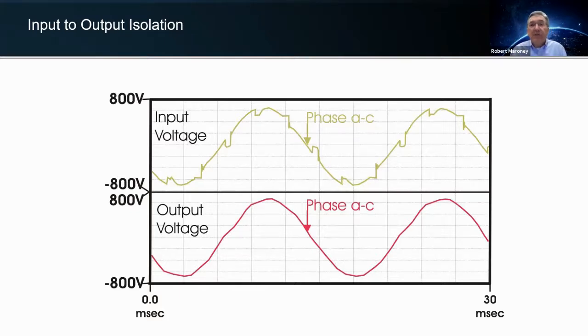Half a hertz off of 50 hertz, and that is adjustable, how sensitive your voltage and frequency are. We can adjust that tolerance from 1 to 15%, actually 20% low. We can go as low as 50% with support from the flywheel before we disconnect as well. But this gives you an idea of how we handle that isolation and what that waveform would look like on the output of the UPS.